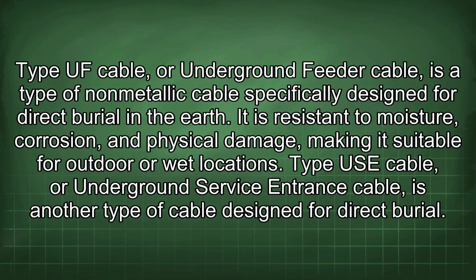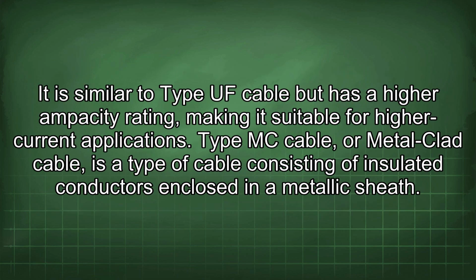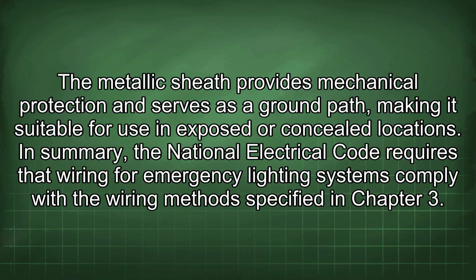these requirements. Type UF cable, or underground feeder cable, is a type of non-metallic cable specifically designed for direct burial in the earth. It is resistant to moisture, corrosion, and physical damage, making it suitable for outdoor or wet locations. Type USE cable, or underground service entrance cable, is another type of cable designed for direct burial. It is similar to Type UF cable, but has a higher ampacity rating, making it suitable for high current applications. Type MC cable, or metal-clad cable, is a type of cable consisting of insulated conductors enclosed in a metallic sheath.